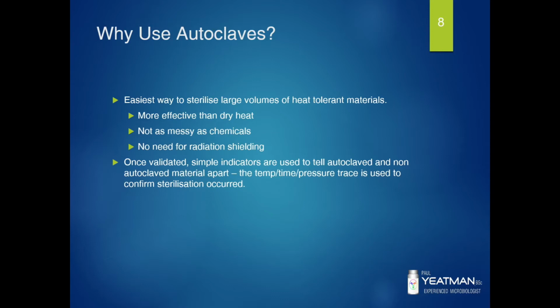So once you've run your autoclave cycle and you've checked the temperature traces and pressure traces to confirm that the cycle is actually valid, unload the autoclave and put the items in the resting area. Even though the wrap might be moist or wet at this point, give it 5-10 minutes and it'll be dry.